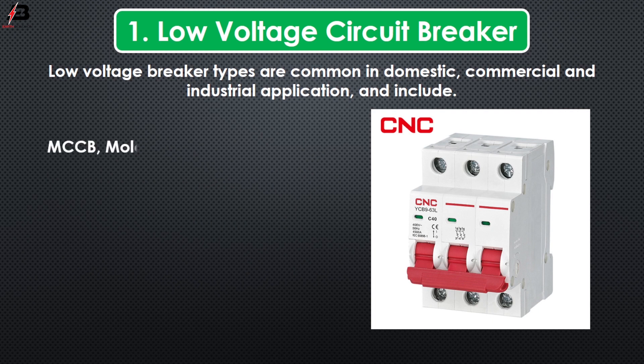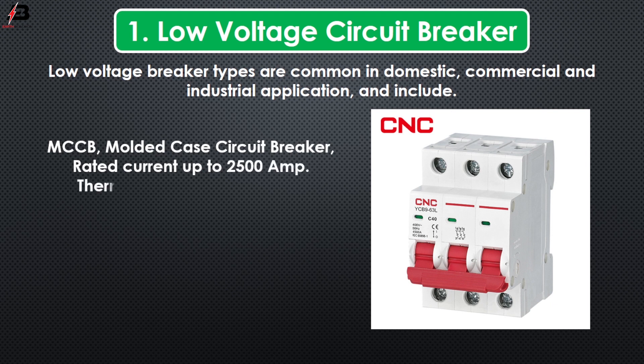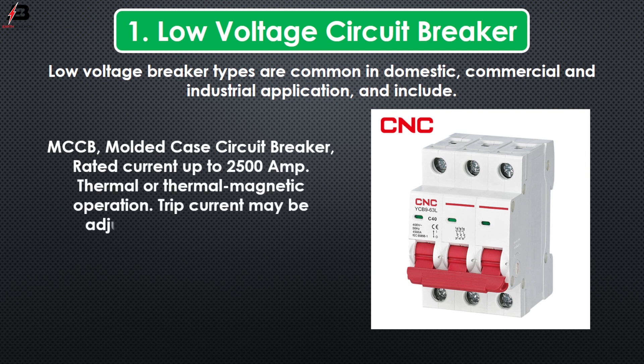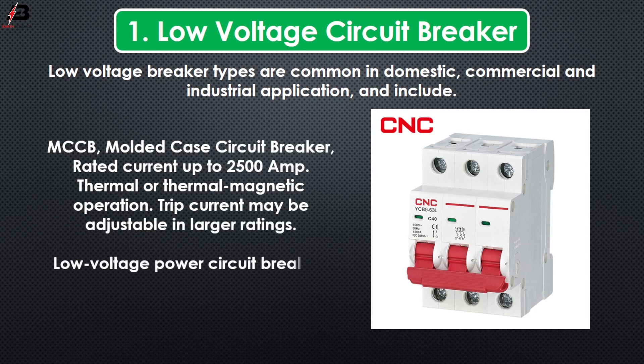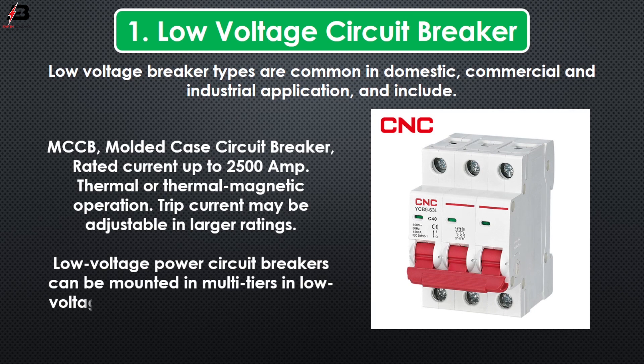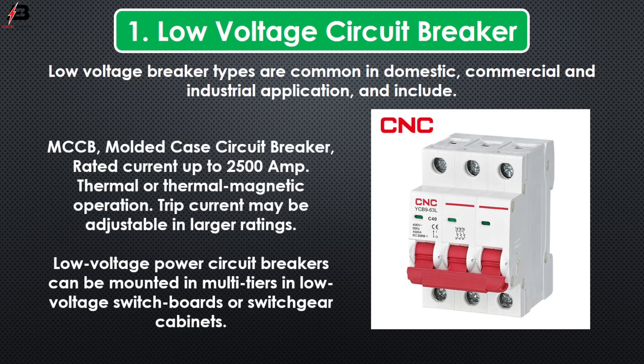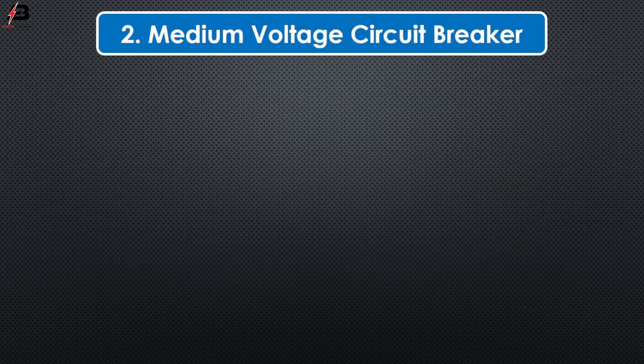MCCB — Molded Case Circuit Breaker. Rated current up to 2500 amperes. Thermal or thermal magnetic operation. Trip current may be adjustable in larger ratings. Low voltage power circuit breakers can be mounted in multi-tiers in low voltage switchboards or switchgear cabinets.